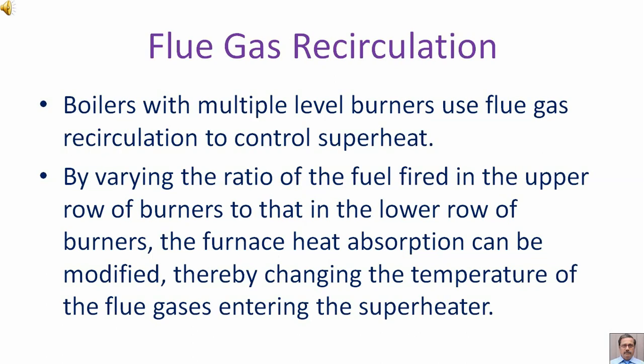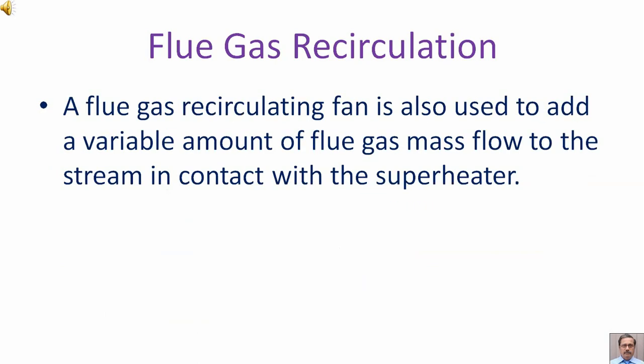Flue gas recirculation. Boilers with multiple level burners use flue gas recirculation to control superheat. By varying the ratio of the fuel fired in the upper row of burners to that in the lower row of burners, the furnace heat absorption can be modified, thereby changing the temperature of the flue gases entering the superheater. A flue gas recirculating fan is also used to add a variable amount of flue gas mass flow to the stream in contact with the superheater.